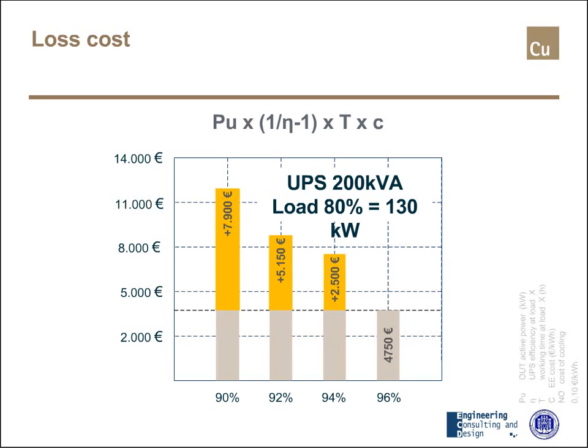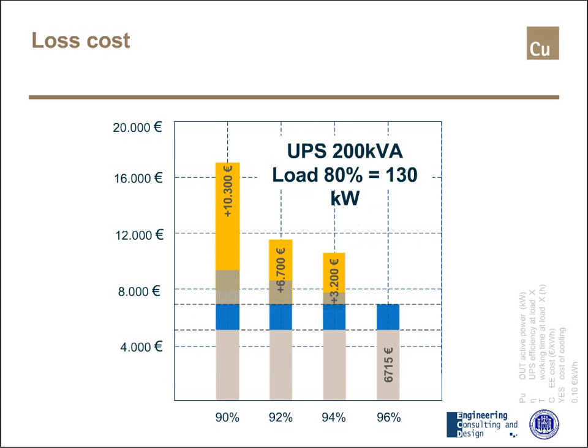This calculation did not include the cost of energy for the cooling system. As losses increase, cooling requirements increase, and cooling is usually performed with electrical equipment. If the COP of the cooling system is approximately 3, we must add about 30% to this cost. UPSs work 24 hours a day, seven days a week, so efficiency is a very important issue to consider when specifying them.